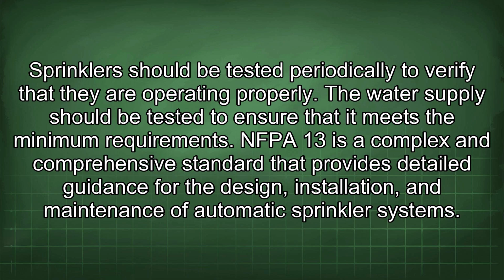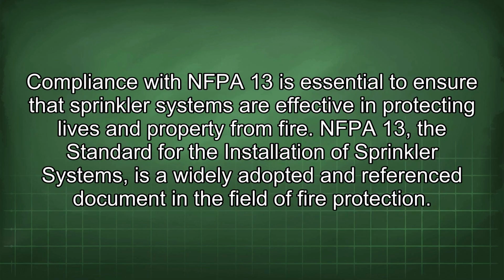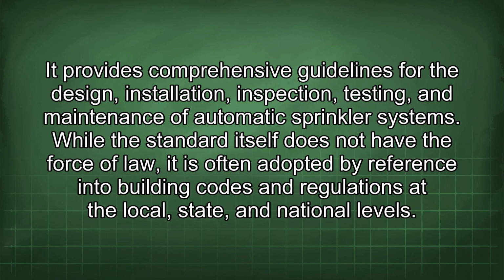NFPA 13 is a complex and comprehensive standard that provides detailed guidance for the design, installation, and maintenance of automatic sprinkler systems. Compliance with NFPA 13 is essential to ensure that sprinkler systems are effective in protecting lives and property from fire. NFPA 13, the standard for the installation of sprinkler systems, is a widely adopted and referenced document in the field of fire protection. It provides comprehensive guidelines for the design, installation, inspection, testing, and maintenance of automatic sprinkler systems.